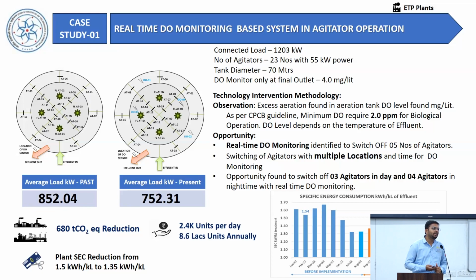After the implementation of this ECM, there is an opportunity to switch off four agitators or aeration blowers at night time and three agitators at daytime. Implementing this best practice, the industry was able to achieve a power consumption of 752 kilowatt. It is equivalent to 2400 units savings per day. So it is a significant energy savings achieved by the industry using this energy assessment.